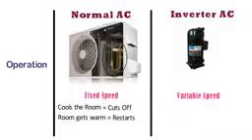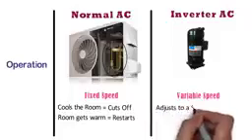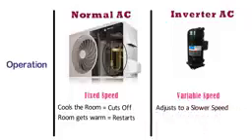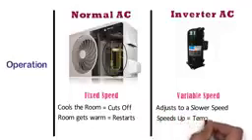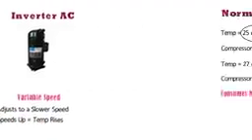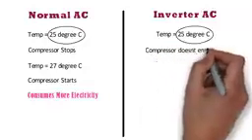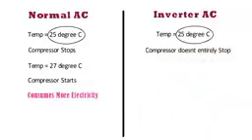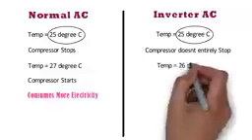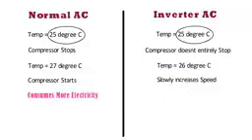In inverter air conditioners, the compressor runs at a variable speed, which means it adjusts to a slower speed when the desired temperature is achieved, and speeds up when the temperature rises. For example, if you set 25 degrees and it is achieved, the compressor doesn't entirely stop but maintains a minimum speed, and when the temperature rises to 26 degrees, it slowly increases speed and brings it back to 25 degrees.